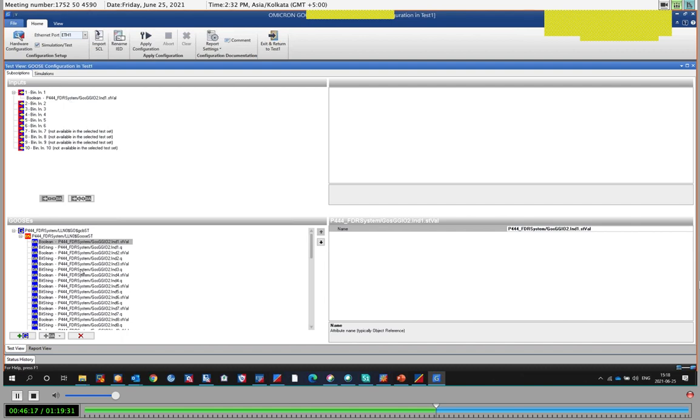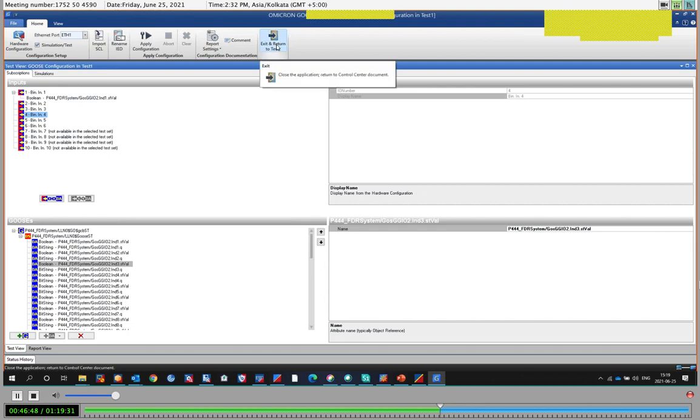We can map multiple GOOSE, such as, let's say, this indication 3 to, let's say, the fourth input. And I can even define virtual inputs and outputs, so I can have 256 and even more using Relay Simulator. I can have multiple GOOSE data attributes mapped. Most of the cases we require 1 or 2 or maybe 5, 10 if you are using it for different phases. Currently, I will use this one. So this is the only thing I have to do for the mapping part.